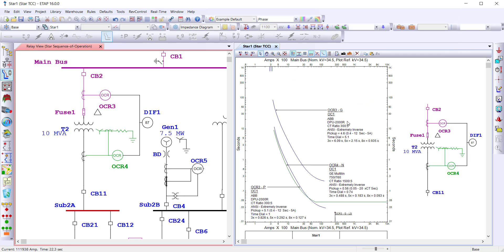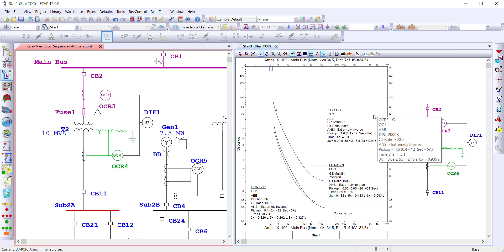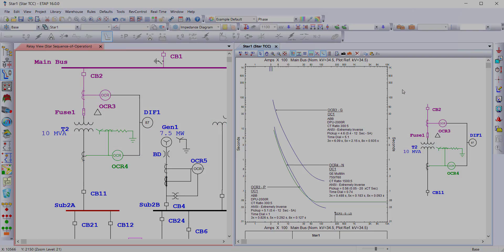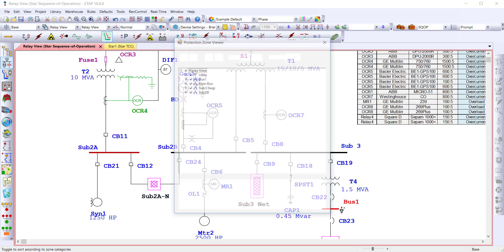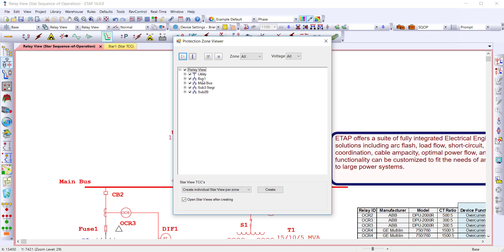Switch to ground mode to view the phase and ground functions together on the same coordination study. Now that we've looked at some of the features within the TCC study, let's look at another tool for helping create one. Utilize the path detection tool to automatically identify and define a protection coordination path. This tool allows you to select an element while automatically defining the zones required.